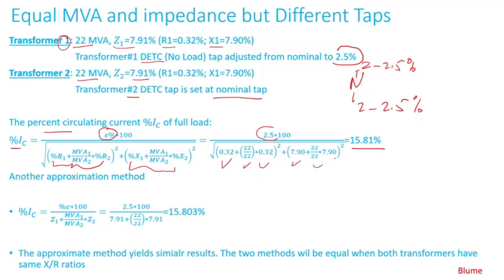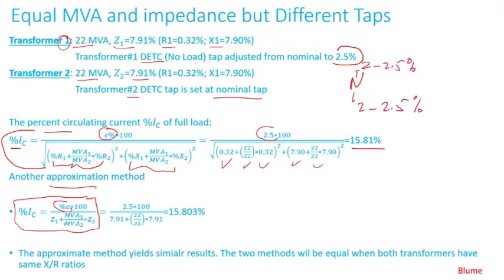There is also an approximation method. When transformers are large, impedance is very close to reactance, and when the X/R ratios are very similar, you can simplify: take the voltage difference in percent divided by the impedance of Transformer 1 plus the MVA ratio times the impedance magnitude of Transformer 2. Plugging in the numbers gives very close results to the exact method.